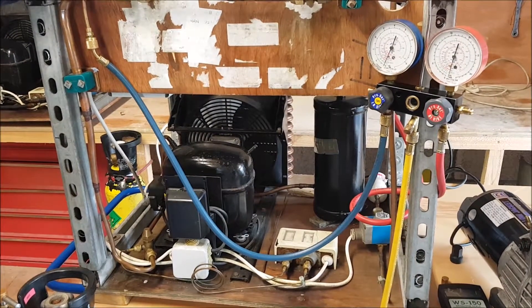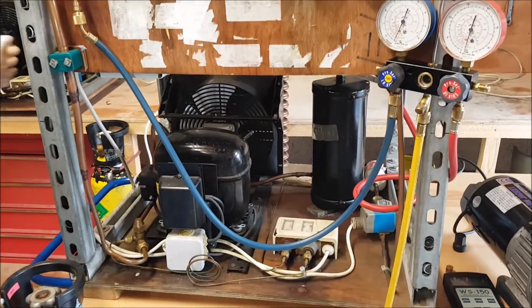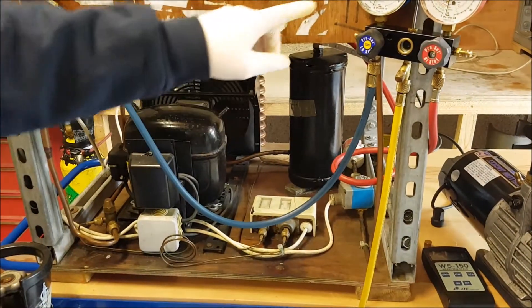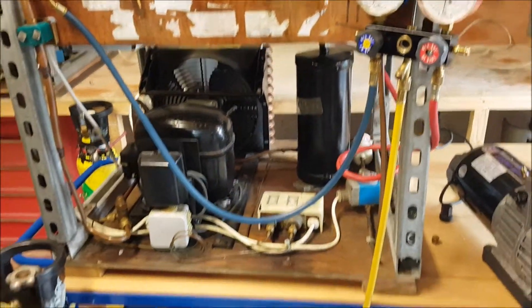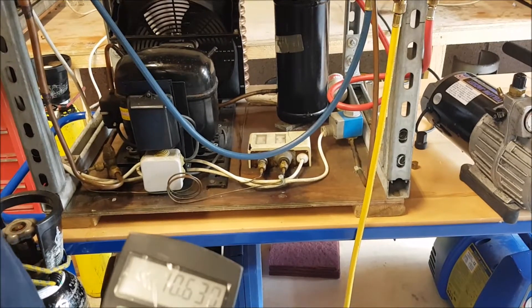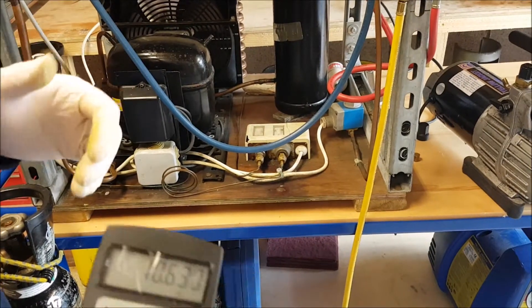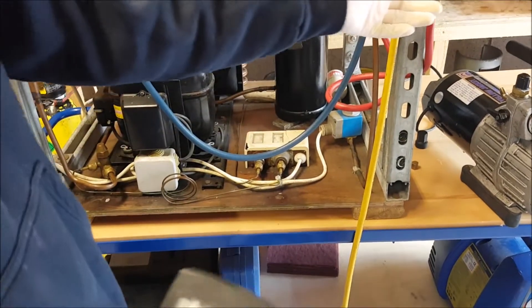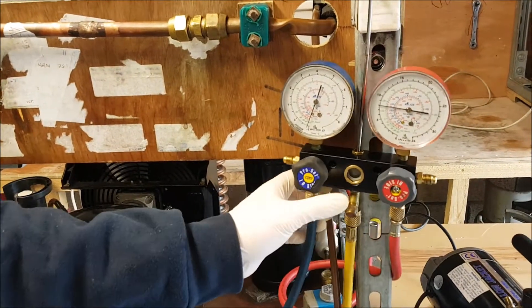Getting back to this, I'm going to knock off my solenoid. My solenoid is de-energized. That means that only the refrigerant will go as far as the solenoid valve, won't go anywhere else. I keep an eye on my weighing scales as well. I want to make sure that I don't overcharge the system. Therefore, I would know what the weight of refrigerant is prior to me actually charging the system. Then I would bomb charge.